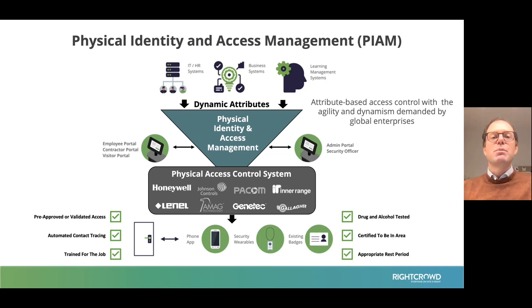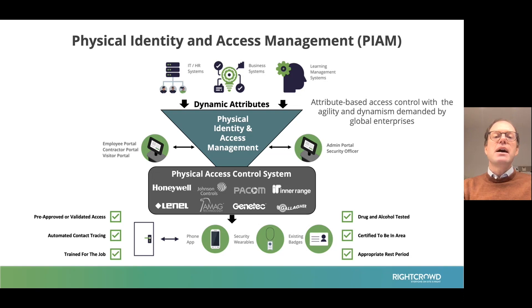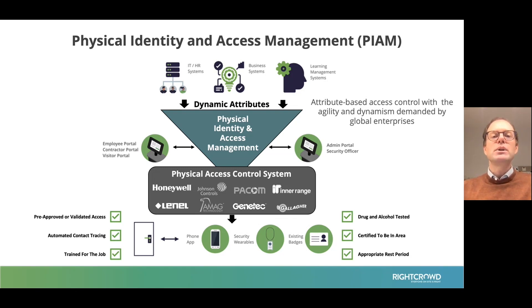The second benefit of using a PIAM system is the ability to move away from statically defining access to dynamically assigning access. The best way to explain that is by means of an example. Today, let's say you have an IT department of 10 people. If you want to assign access rights to the data center for those people, you would go into the physical access control system and name by name assign the access rights to the data center. It's manual and you assign it person by person.